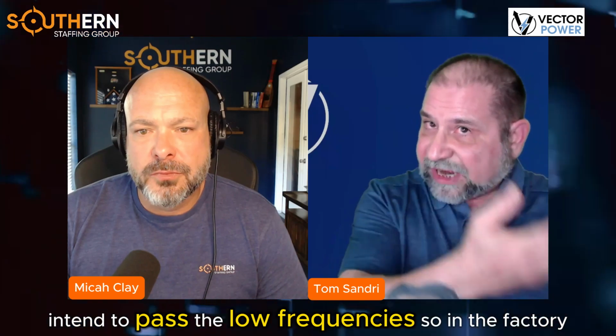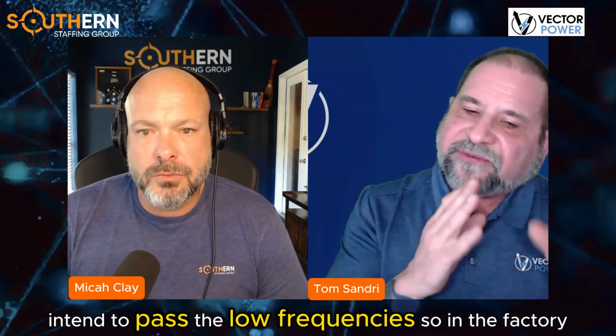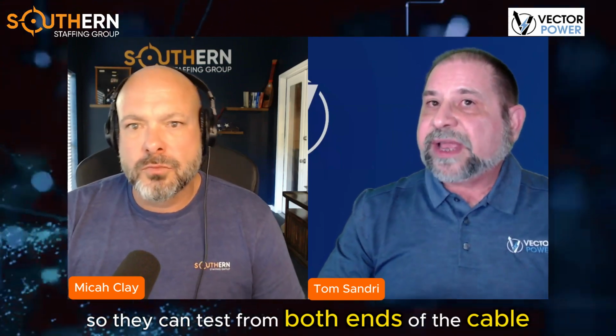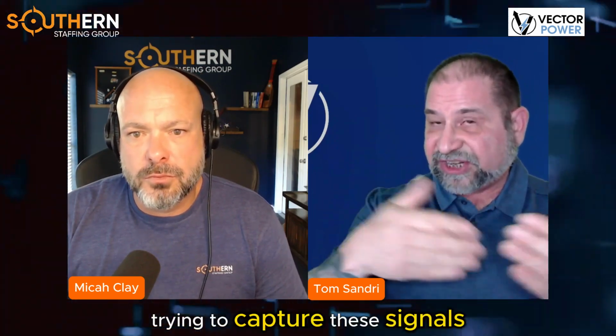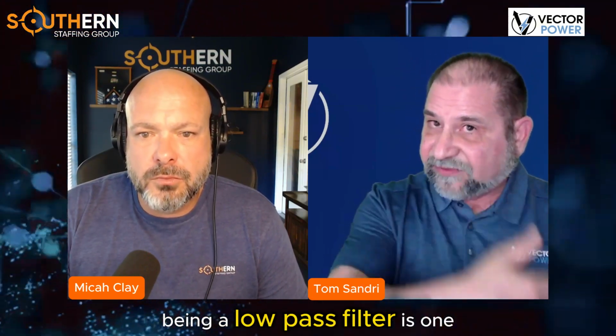These transients, these signals that are being produced, are high frequency in nature. I mean, they're up in the upper megahertz bands. Now, there's a reason why the electrical utilities deliver 60 hertz power and they don't deliver high speed internet. Power cables are low pass filters. They absorb the high frequencies and tend to pass the low frequencies. So in the factory, they're not concerned with mapping the location of where the PD is being created. They can test from both ends of the cable and they're just looking for the presence of PD, but they're not trying to capture these signals, measure time delay between reflections, and do mapping.